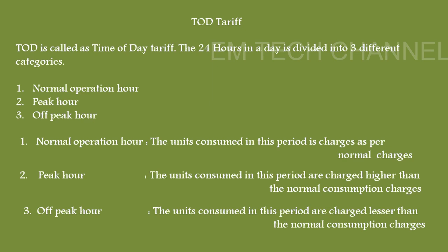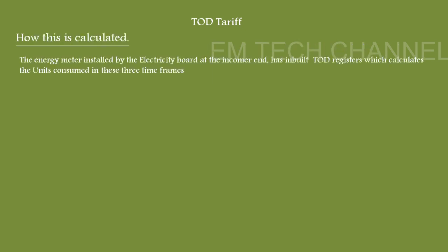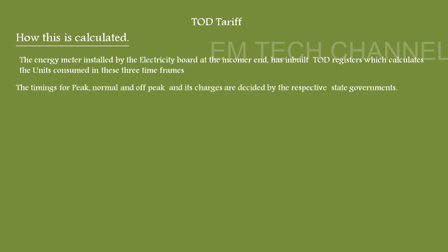The energy meter installed by the electricity board in our facility has a special inbuilt register that is pre-programmed as per the time slots set by the respective state governments. The cumulative energies consumed in each time frame are calculated in these registers, and this data is fetched and used for billing purposes. TOD users are billed across three time frames — peak, normal, and off-peak — and the charges are decided by the respective state governments.